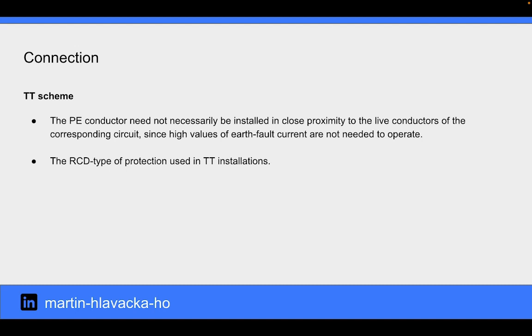In the TT scheme, the PE conductor does not necessarily have to be installed near the live conductors of the corresponding circuit, since high values of earth fault current are not needed to operate the RCD type of protection used in TT installations.